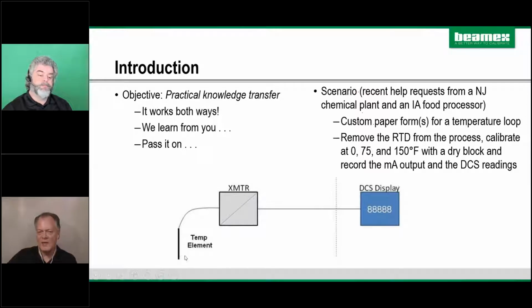Here's what we have: a temperature element connected to the transmitter with 4 to 20 milliamps going into the input card, ultimately displayed to an operator. We're doing 3 things: number 1, providing temperature to this temperature element or probe; number 2, measuring the milliamp output of that transmitter; and number 3, recording the value on the DCS display in the control room. So our critical readings are the temperature, the milliamps coming out, and the display.